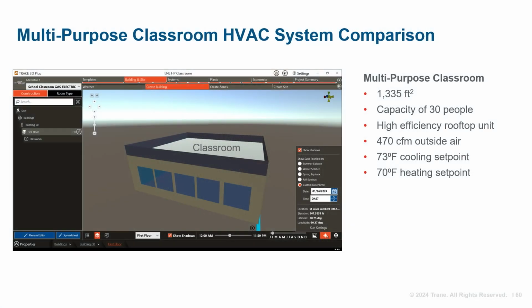Now let's look at a real-world example of a classroom across many geographies and ASHRAE climate zones to compare various rooftop system configurations. In our example, we have a single 30-person multi-purpose classroom being served by a single high-efficiency rooftop unit with 470 CFM of outside air based on ASHRAE 62.1 and a desired space temperature of 73 degrees Fahrenheit for cooling and 70 degrees for heating.